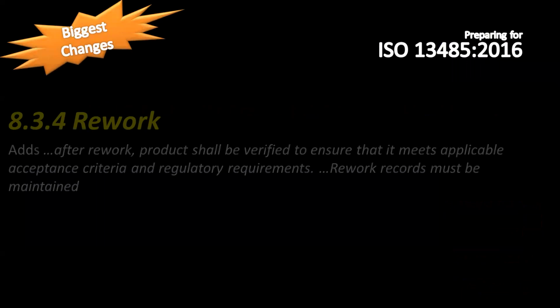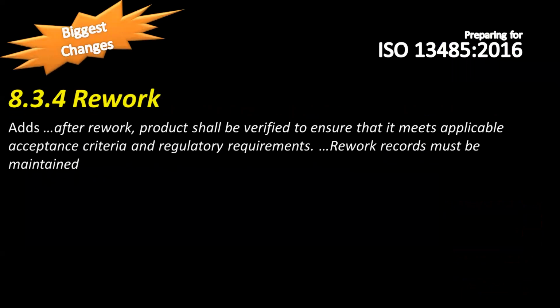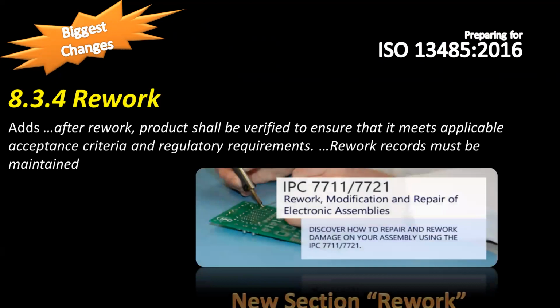That's another requirement. Rework is a new section. Again, FDA has had this for a while. So for companies that are complying with the quality system regulation, this won't be that new. It adds that after rework, products shall be verified to ensure that they meet the applicable acceptance criteria and the regulatory requirements. And those records, of course, must be maintained.